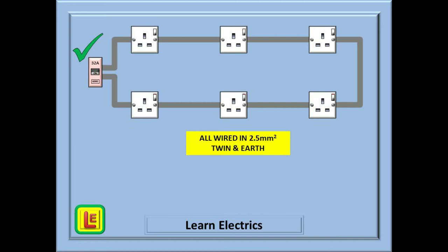Let us begin with a standard ring circuit as you would find in most domestic properties in the UK. We can see here that the ring is protected by a 32 amp breaker and that the wiring is in 2.5mm twin and earth cable.